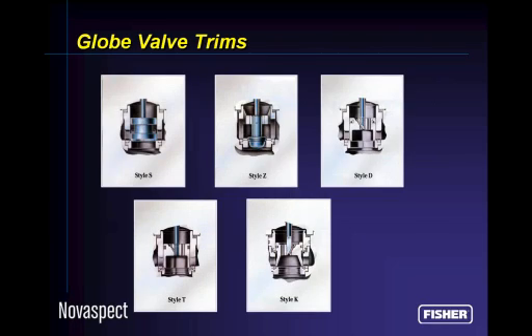If you were to look at the internal valve trim components in the valve, there are various different forms. We call them balanced trims, unbalanced trims. They're guided with cages. They're guided with bushings. A lot of different styles depending on the application. But what you need to realize is that it's nothing more than a variable orifice. The blue element, the plug, moves up and down as commanded by the actuator, as commanded by the positioner, as commanded by your control system. And we move the plug more or less against the seat ring, and it's just a variable orifice.